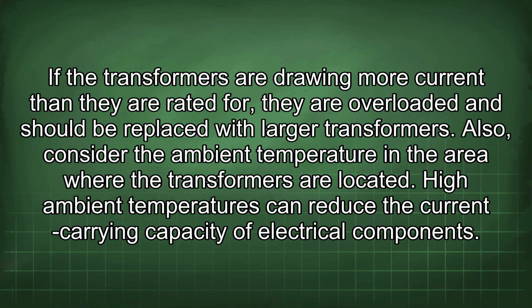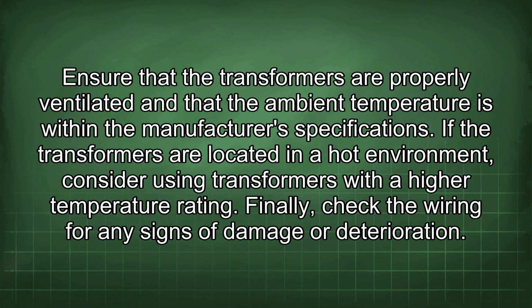Also, consider the ambient temperature in the area where the transformers are located. High ambient temperatures can reduce the current carrying capacity of electrical components. Ensure that the transformers are properly ventilated and that the ambient temperature is within the manufacturer's specifications. If the transformers are located in a hot environment, consider using transformers with a higher temperature rating.